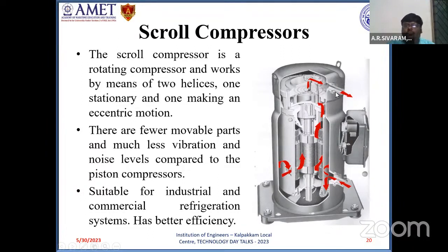Since there are very few movable parts, the noise level as well as the vibration in scroll compressors is very low when compared with other compressors such as piston compressors. This is more suitable for industrial and commercial refrigeration systems.